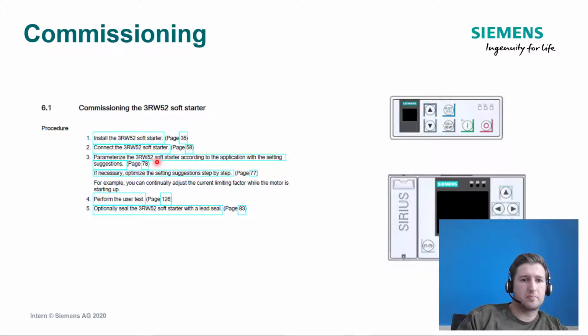the overload protection, which would be depicted by the nature of your application. So how long would it take for the motor to start? If it takes less than 10 seconds, you select class 10. If it's up to 20 seconds, class 20, and so on. The next potentiometer is the ramp up time, so how long is it going to take to ramp up, and the starting voltage.